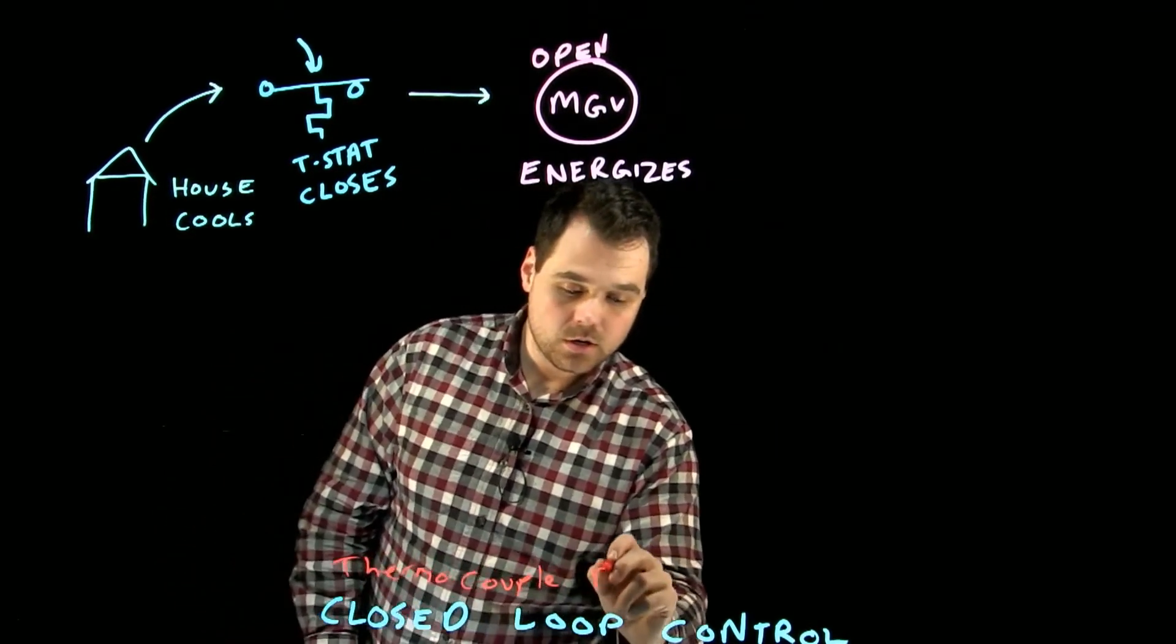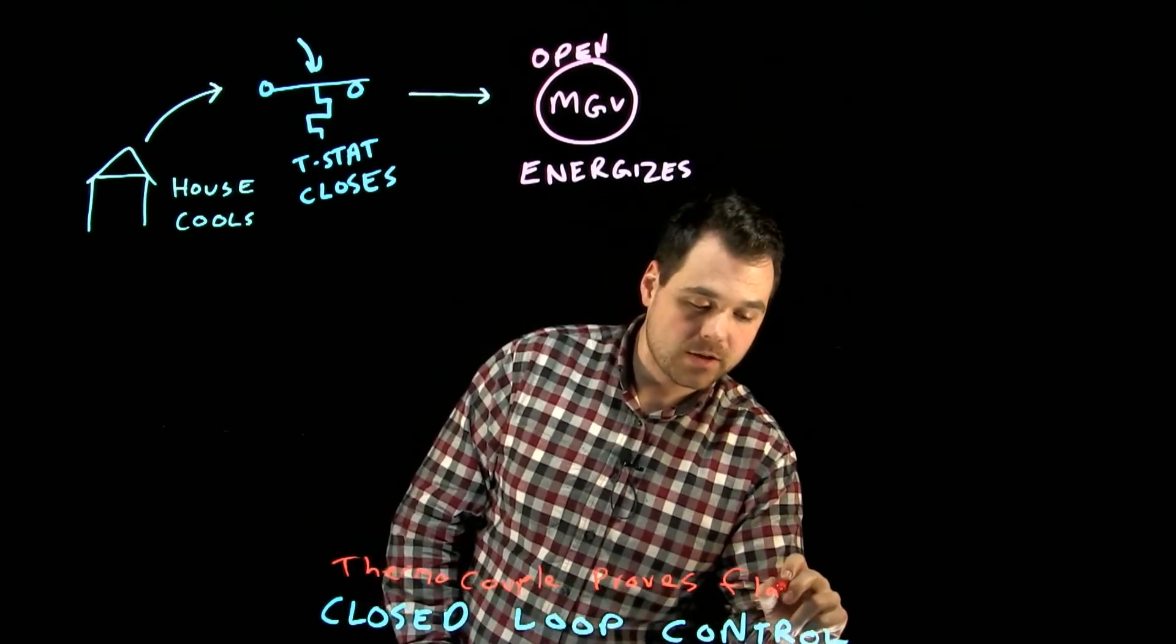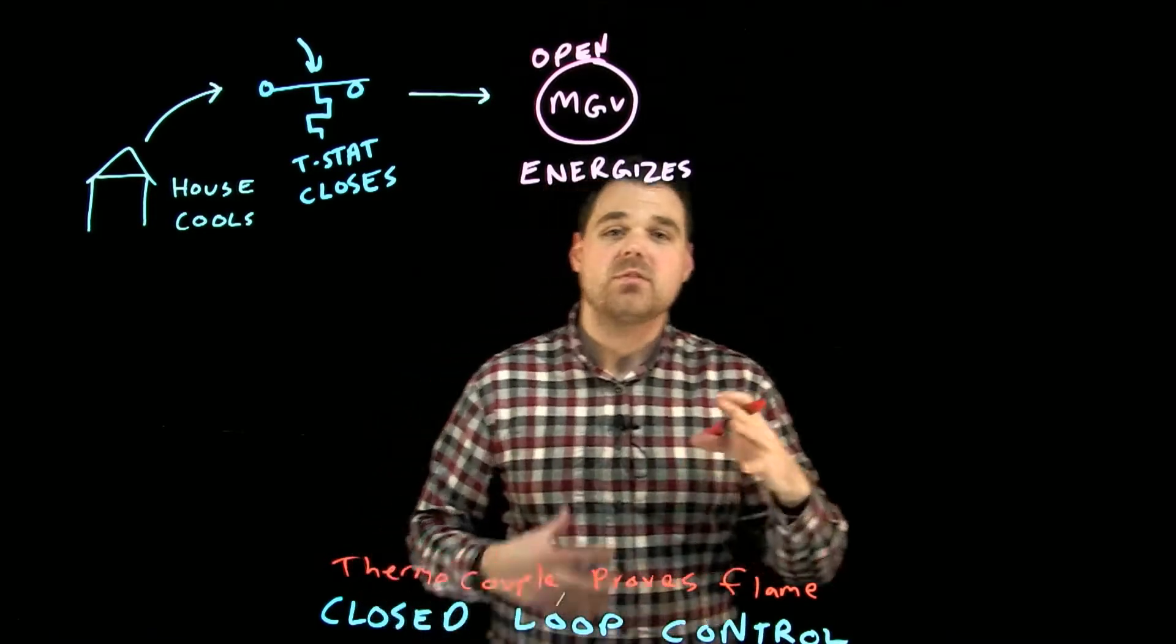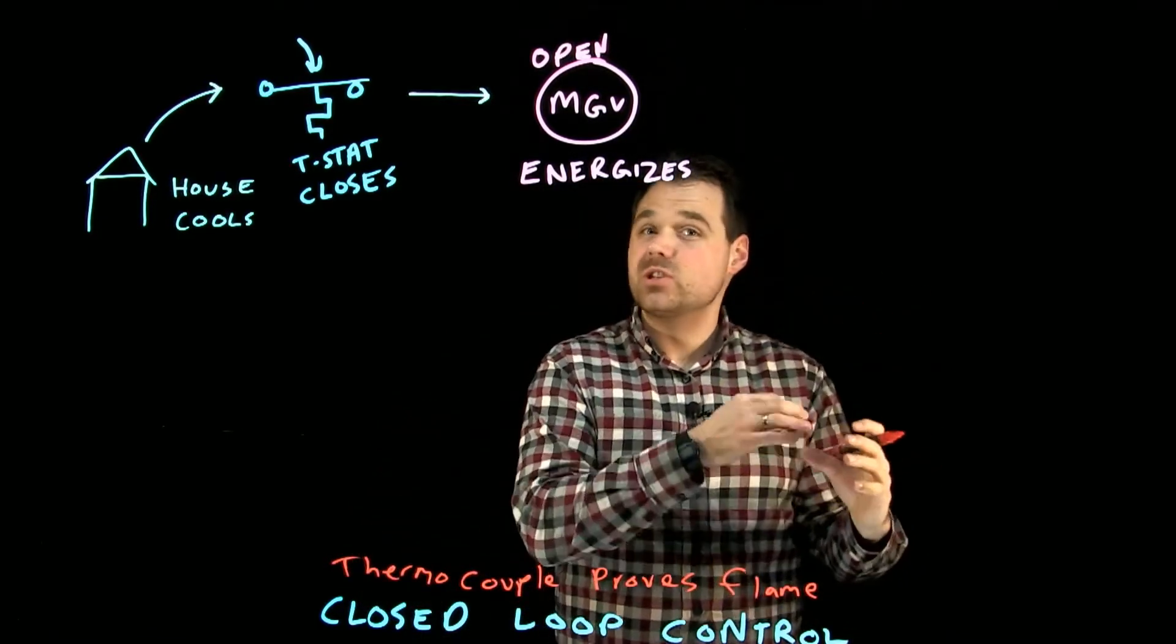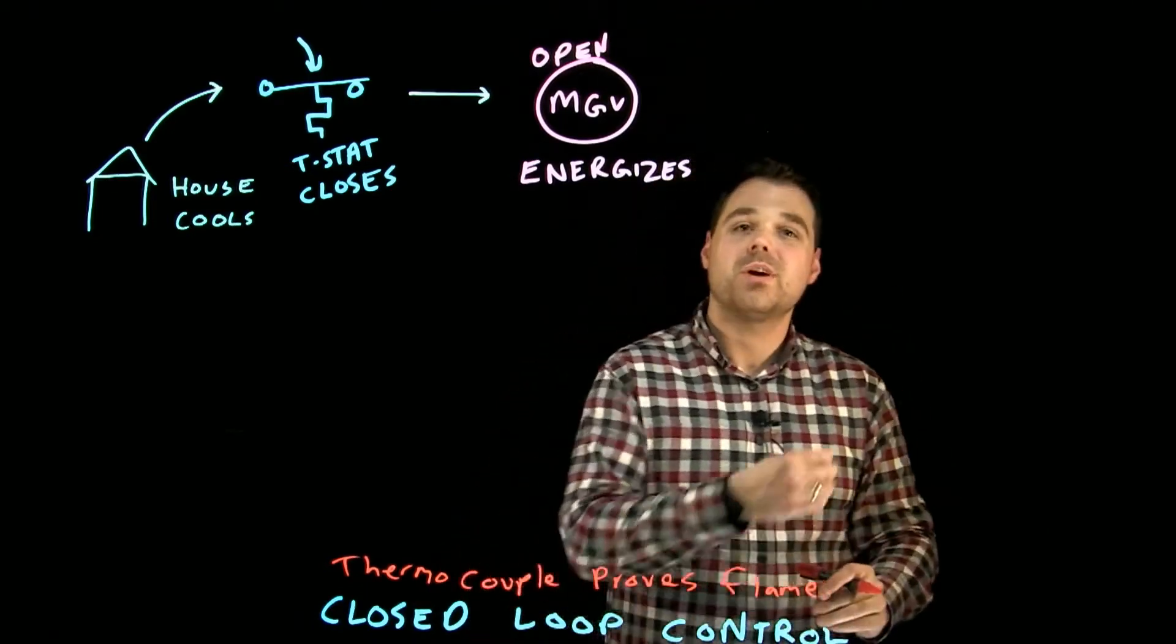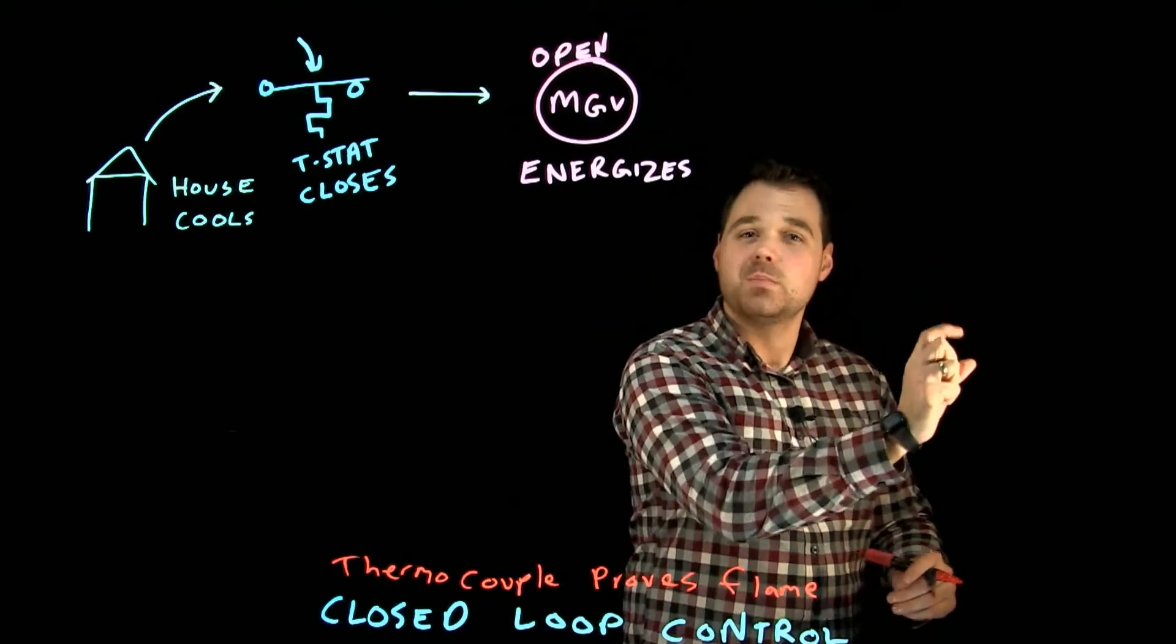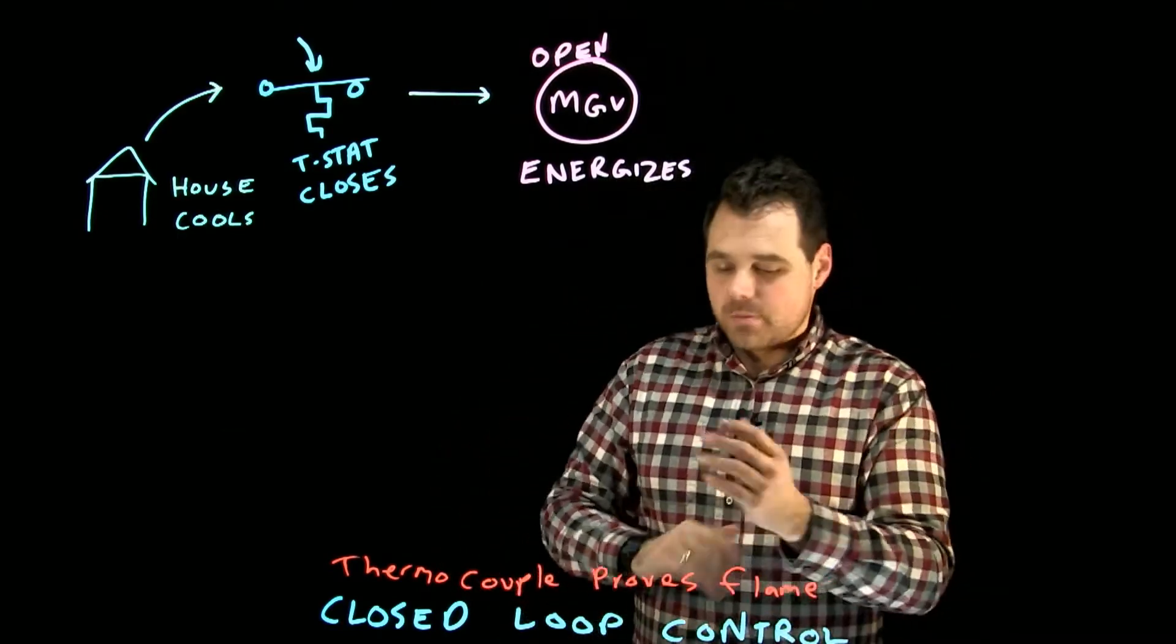If the thermocouple wasn't there proving the flame, then that gas valve, the safety gas valve which is not an electronic component, would actually close. This thermocouple is providing power to that power unit, keeping that safety gas valve open, so our main gas valve opens.